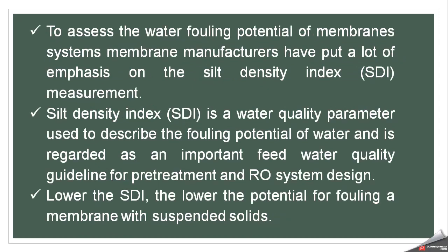Now, to assess the fouling potential of water in a membrane system, membrane manufacturers put a lot of emphasis on the silt density index, SDI, measurement, and they have provided some important values of SDI. Silt density index, SDI, is a water quality parameter used to describe the fouling potential of water, and it is also regarded as an important feed water quality guideline for pre-treatment.